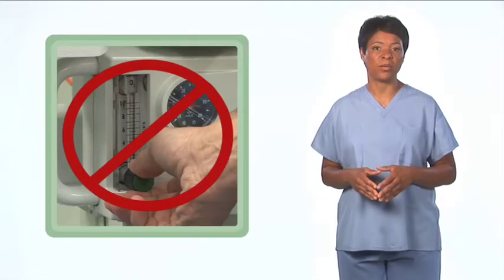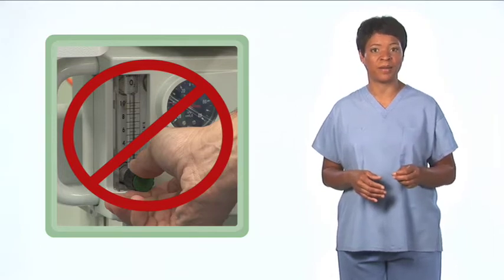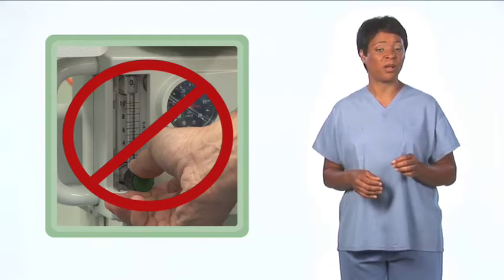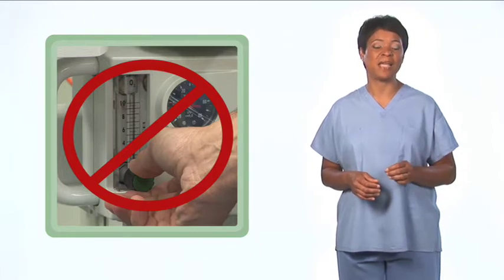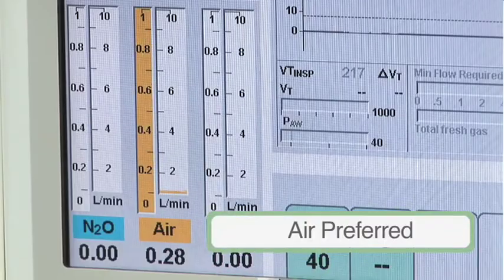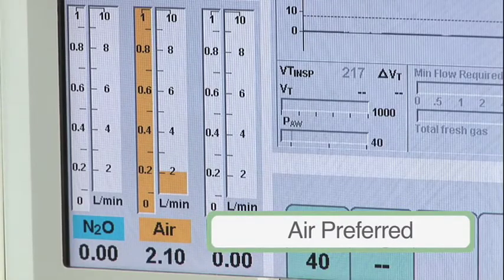When delivering oxygen by nasal cannula or mask in such exceptional cases, you should not use the auxiliary oxygen flow meter, which is only capable of delivering 100% oxygen. The goal is to deliver the minimum concentration of oxygen necessary to maintain adequate oxyhemoglobin saturation. Restricting the delivered oxygen concentration to 30% or less will minimize fire risks during exceptional surgeries and may provide an acceptable oxyhemoglobin saturation, but room air is preferred whenever possible. There is no risk of a flash fire if the oxygen concentration is less than 30%, but many items that do not burn in air will burn in 30% oxygen.